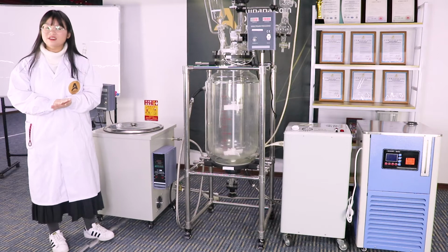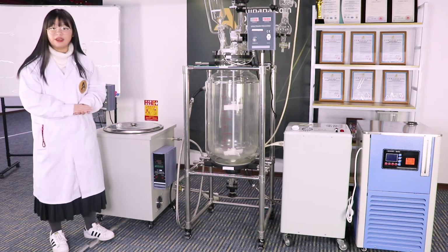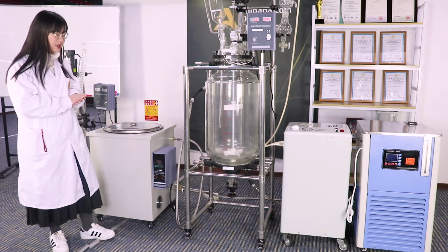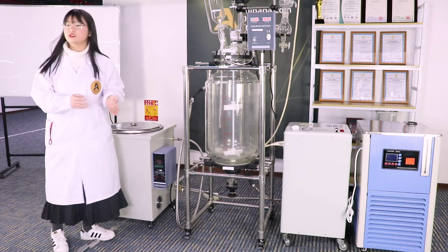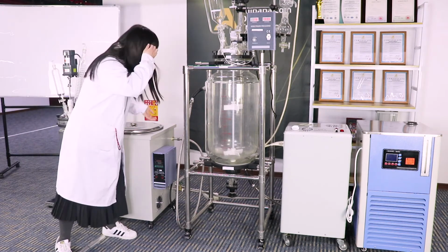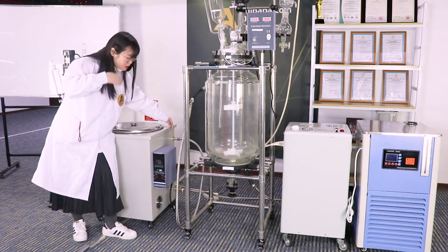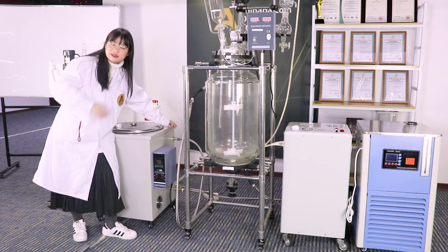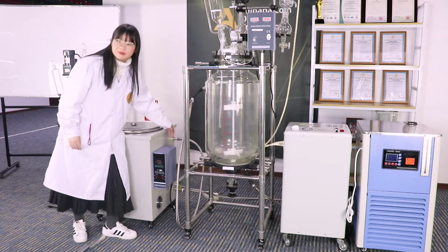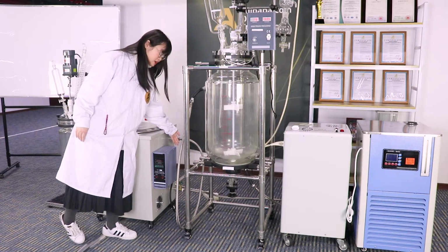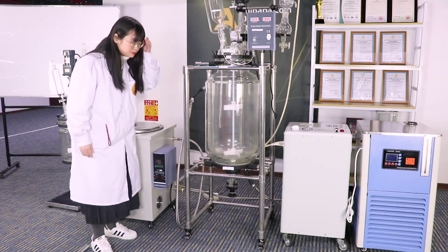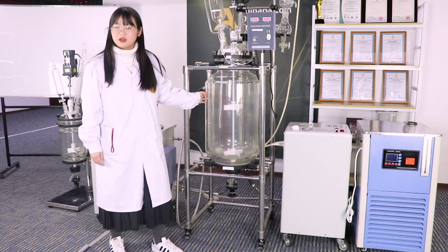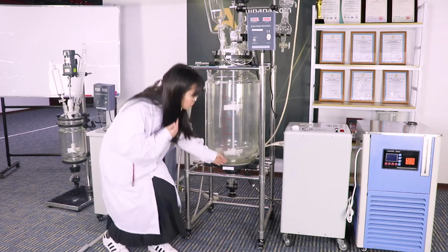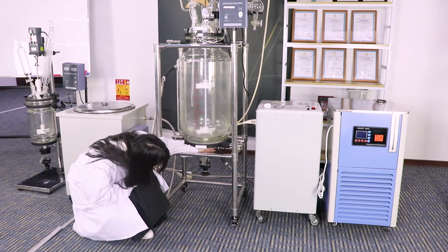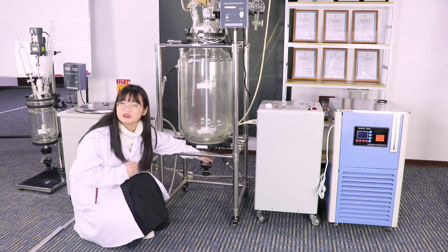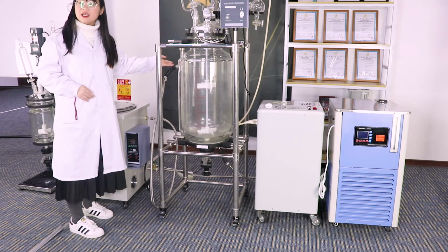When you want to connect the heating bath with the glass reactor, first I will introduce the ports. This is the top one, the heating bath inlet. The below one is the heating bath output. The glass reactor inlet is at the bottom of the reactor. Here is the jacket inlet, and this one is the jacket outlet.